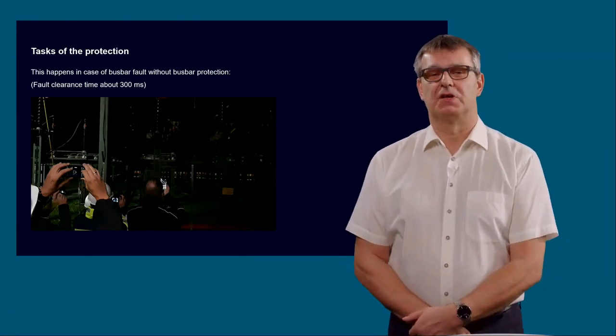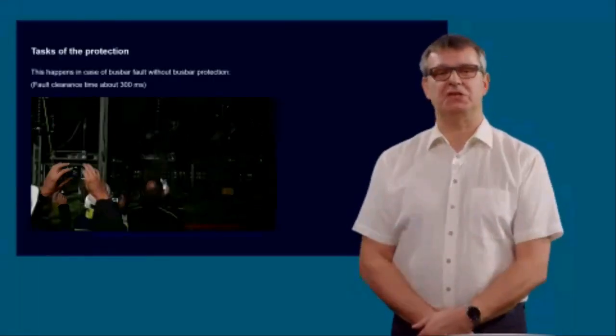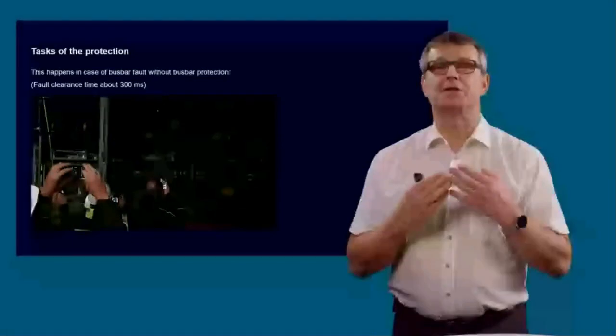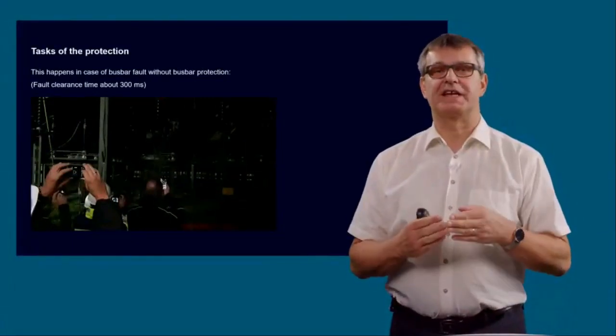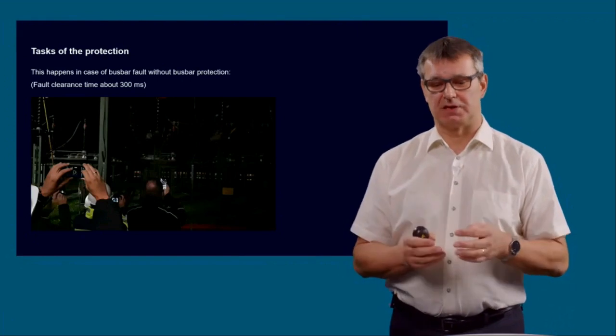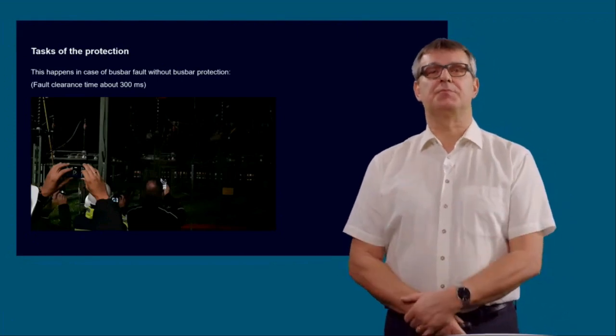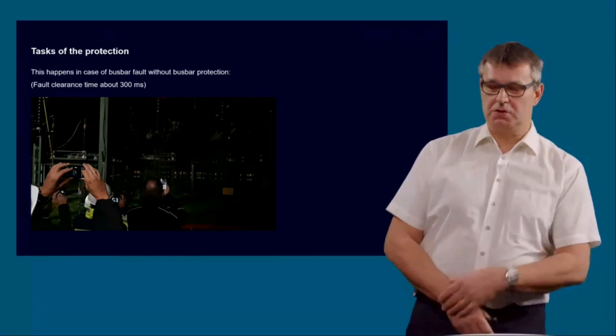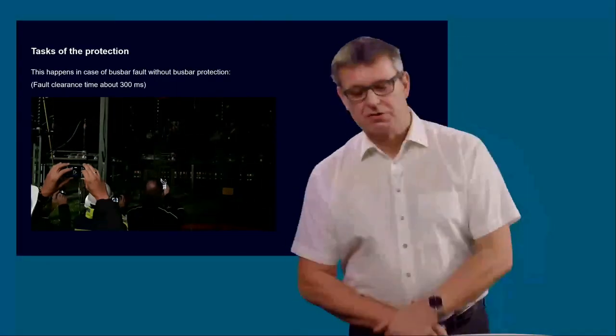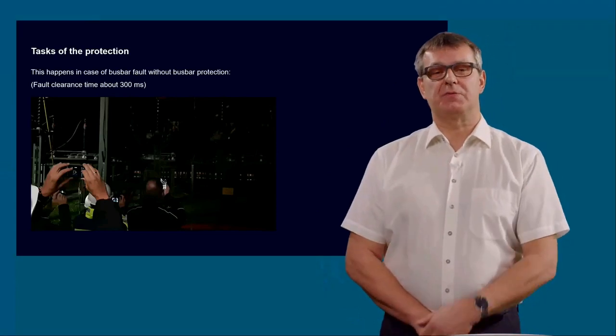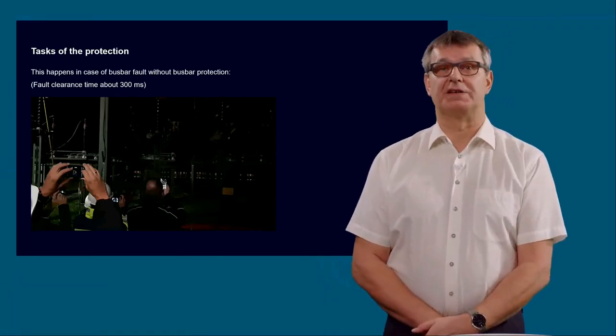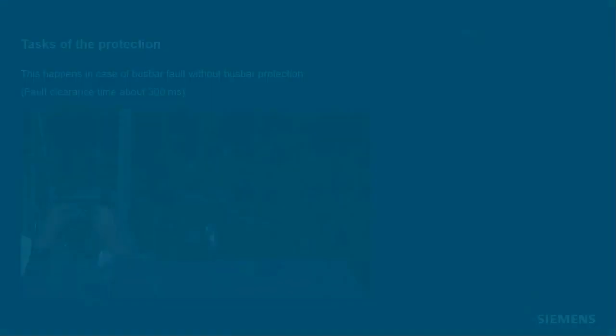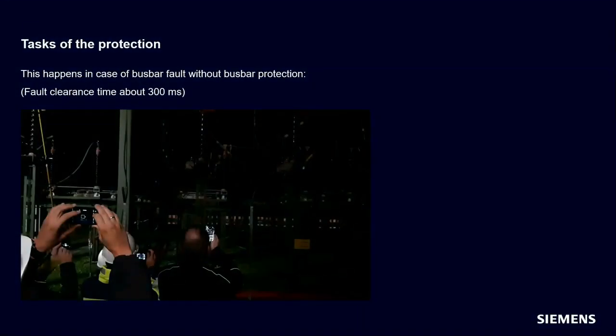And what we see now is what happens if we have no dedicated busbar protection and we have only a backup protection, and in this case it was a distance protection in the reverse zone with a clearing time of 300 milliseconds only. In former times they had protected the busbar with the 7SS52, and I personally could block the 7SS52 so that we have a fault clearance time of about 300 milliseconds only. And let's see what happens if we have a high destructive busbar fault without dedicated busbar protection.